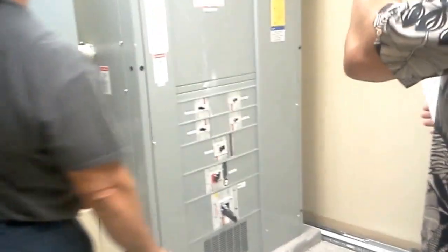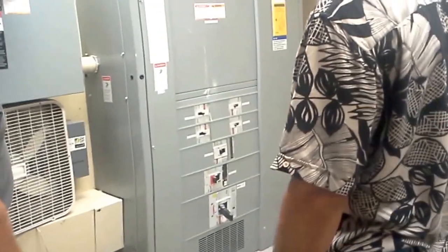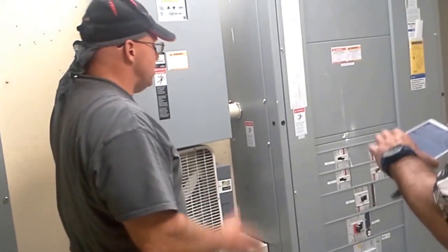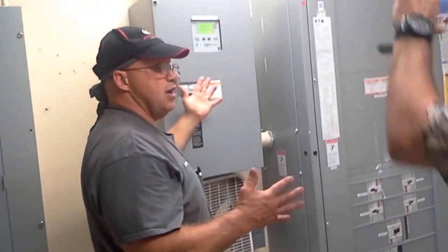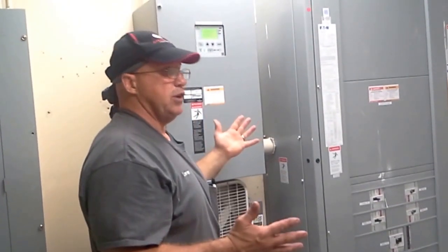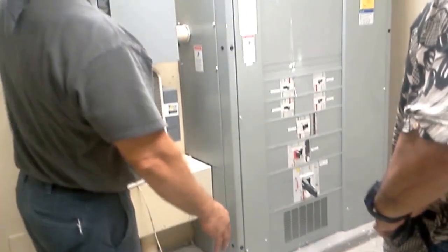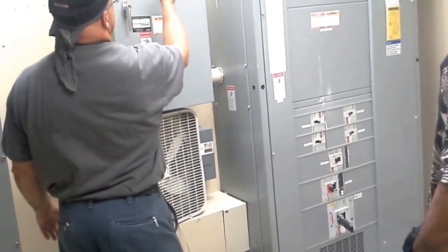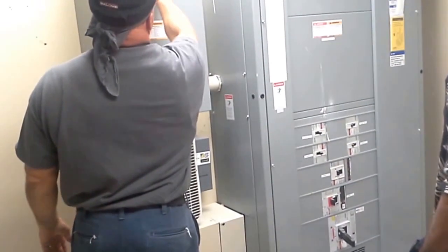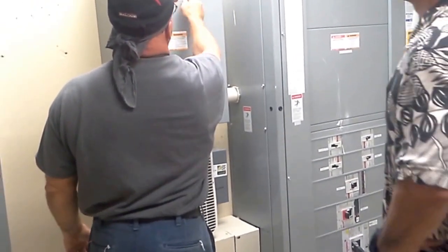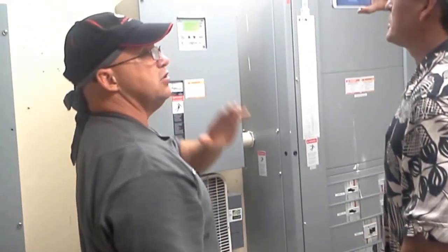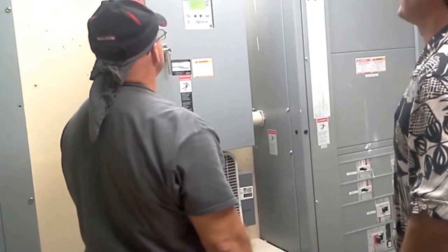But there's a way you can test this just by pushing this and entering your password up here. Okay, that's to exercise. That's just to simulate a power failure without actually having a power failure, without tripping that. Okay, your password is always 1111. So I'm not going to do it because it'll end up starting it up. But I'll push 1, enter, 1, enter, and I'll do it 2 more times, and it'll start up and it'll do the transfer. Okay.